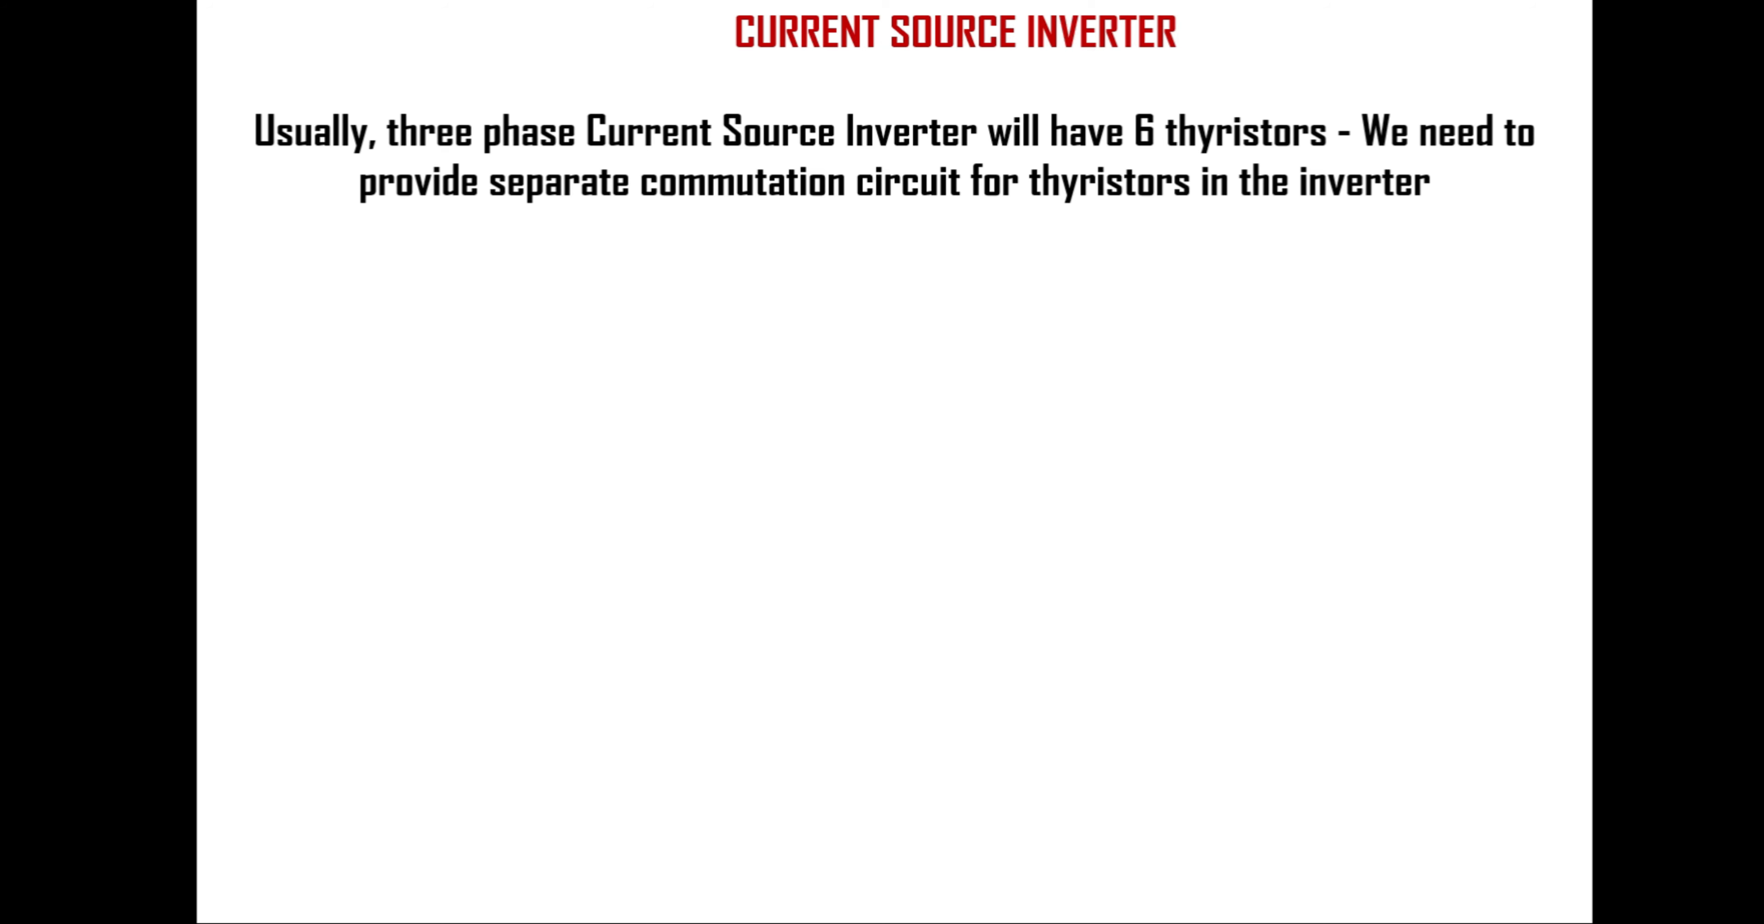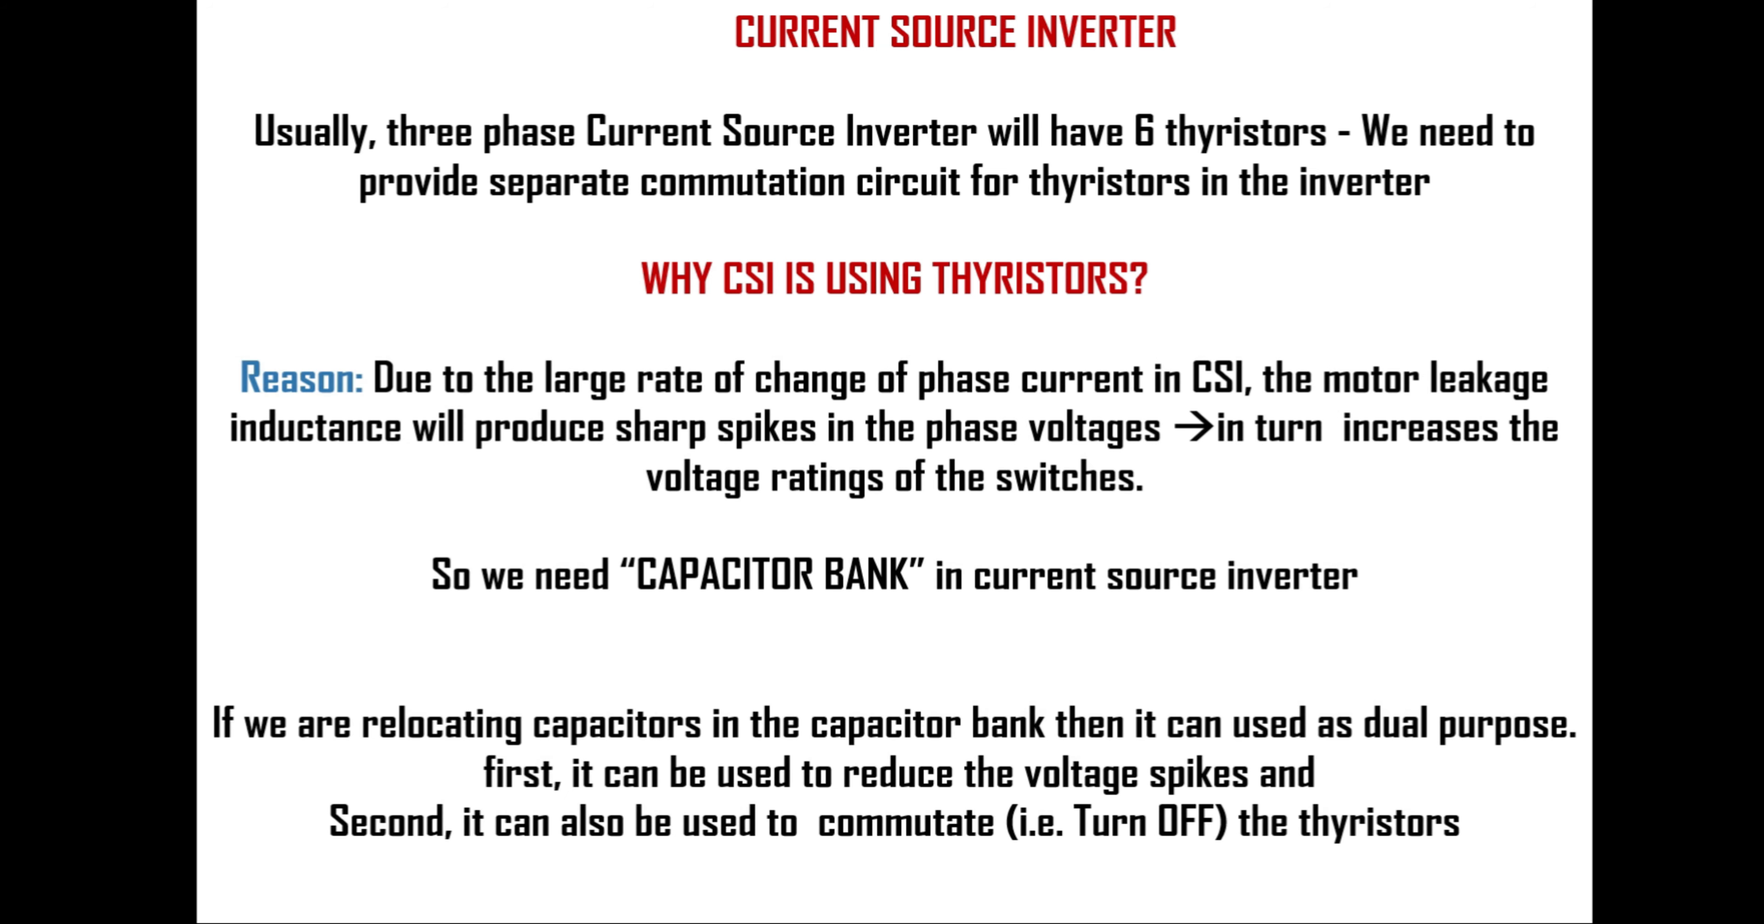Before seeing the commutation circuit let's see why current source inverters are using thyristors. Due to switching actions of thyristors there will be a large rate of change of phase currents and hence the motor leakage inductance will produce sharp spikes in the phase voltages. To avoid this we generally provide a capacitor bank in current source inverter.